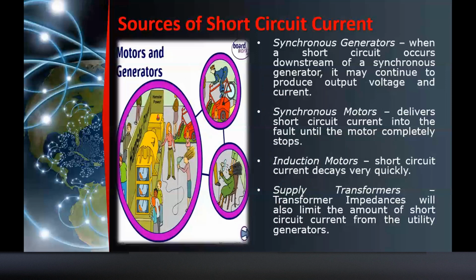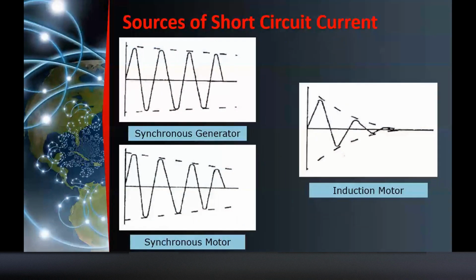So short circuit sources, synchronous generator. When a short circuit occurs downstream of any synchronous generator, it may continue to produce output voltage and current. So hanggat hindi nagte-trip yung generator, it will produce a short circuit. Synchronous motor delivers short circuit current into the fault until the motor completely stops. Okay? So, pag nag-lock na yung motor, hindi na umikot, wala nang torque, tsaka lang siya mag-stop din sa pagbibigay ng short circuit current. Hindi siya katulad ng induction motor, yung current niya or yung short circuit current niya decays very quickly. Okay? Kaya mapapansin niyo yung induction motor, tingnan niyo yung curve, yung graph. Diba? So, nag-decay kagad, ibig sabihin, nawala kagad yung fault current.